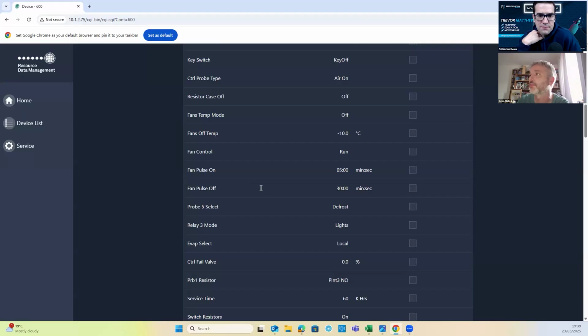This is one to read in the manual. So you can set fans, for example, fans temp mode in there to temp. And then if you get to that temperature, it will switch the fans off. And this is stock protection to a degree. It's really for if the controllers, not the controllers, but the system's failed, right? And you've got a freezer case. If it's not doing any cooling and it's got to -10, there's no point in the fan still being on, is there? Because all you're doing is putting heat in from the fans. So you can tell it to switch the fans off when it gets to that temperature.